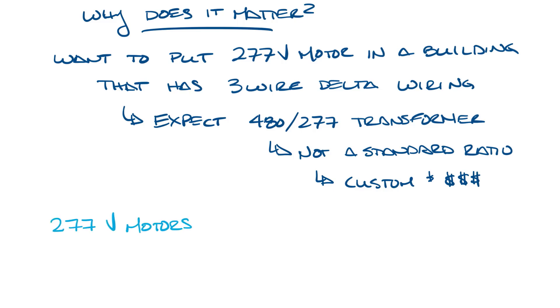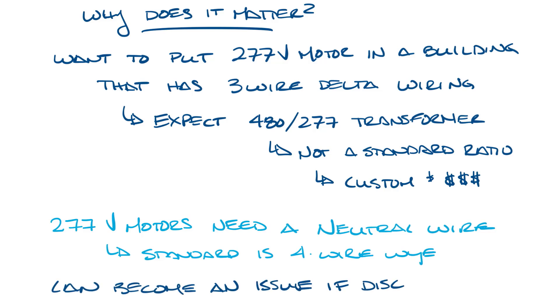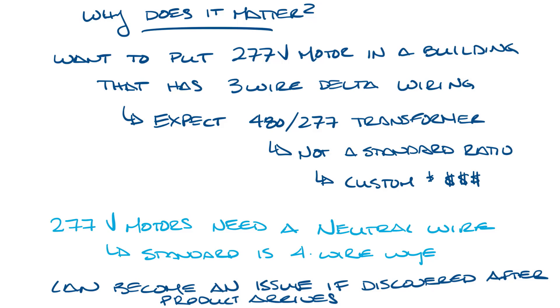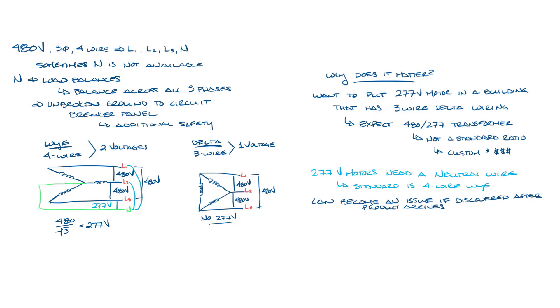So basically, 277 volt motors need the neutral wire, meaning the standard wiring for a 277 volt motor is 4-wire Y. You can see how this becomes an issue if no one realizes that the building electrical doesn't have a neutral until after the product arrives. So it's something you need to be aware of before you order your fan boxes or anything with 277 volt motors. Let's bring all this back on screen. So that covers an overview of 3-wire versus 4-wire wiring and why it matters. Don't forget to subscribe to our YouTube channel, and thanks for watching.